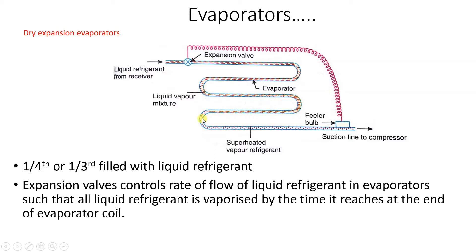In the diagram of the dry expansion type evaporator, evaporator coils are shown. At the beginning, liquid refrigerant comes from the condenser, then through the receiver to the expansion valve. After expansion, the pressure and temperature of the refrigerant decrease and it enters the evaporator. The expansion valve takes feedback from the outlet of the evaporator, controlling the flow rate of refrigerant entering it. If load is less, less refrigerant is sent; if load is more, the feeler bulb gives feedback to the expansion valve and more refrigerant is sent.